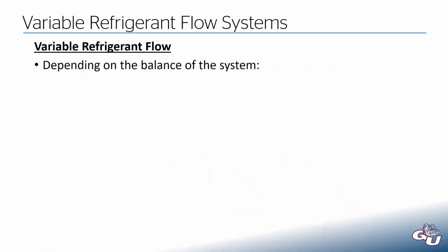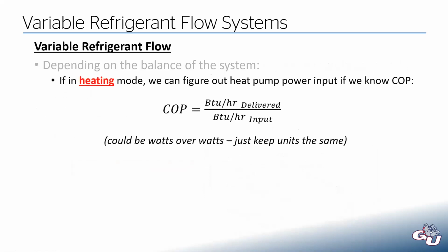Depending on the balance of the system, if we're in that dominant heating mode, we can figure out how much heat pump power we need if we know the COP of that device. So the BTU per hour that we need to deliver, and that's only the balance. Well, if we know the COP, then BTU per hour delivered over BTU per hour on the input side, or you could do watts over watts because COP is dimensionless. Normally, we want to solve for watts because that's how we define electrical power.